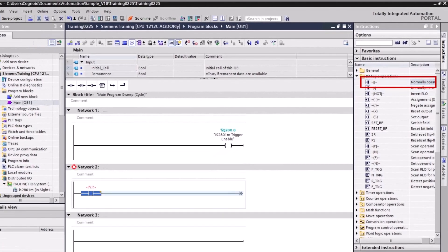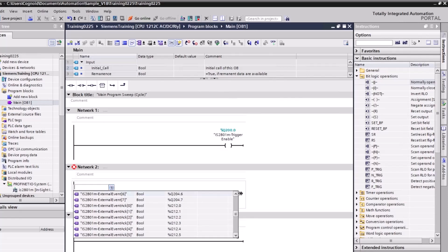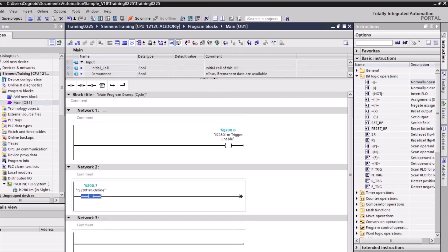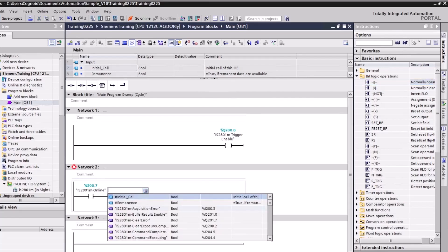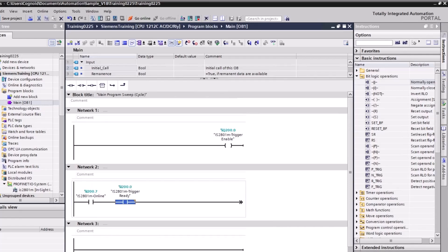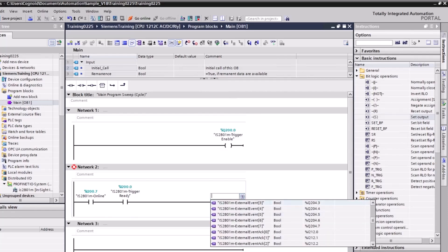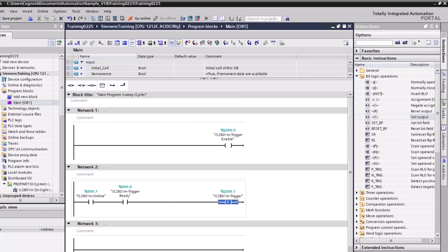Drag and drop a normally open instruction to add an Online instruction to the next rung. Double-click the question mark and select Online from the list. Press Enter, then add a second normally open instruction and add a Trigger Ready instruction to the rung. From the BitLogic operations list, double-click Set Output and select the Trigger instruction. The output is now set.